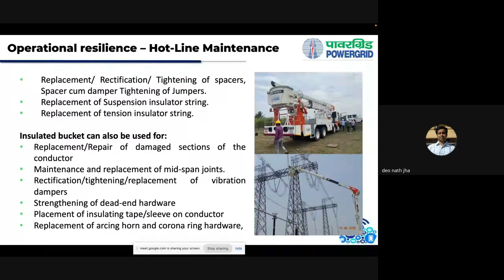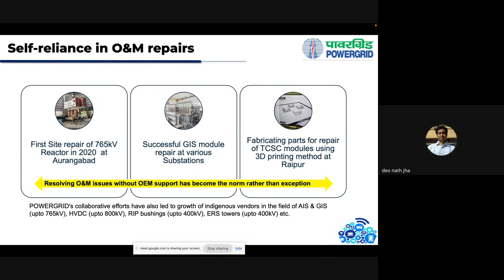In terms of new technology for on-demand repairs, many high voltage equipments are now being repaired at site because high voltage testing kits are now available in India, ensuring successful repair and charging of these assets at substation level itself. Through collaborative efforts with various vendors, we have also developed indigenous capacity in the field of AIS and GIS up to 765 kV, HVDC up to 800 kV, and RIP bushings and ERS towers up to 400 kV. All these are now available indigenously in India, and we are not dependent on any foreign country for sourcing these equipments.